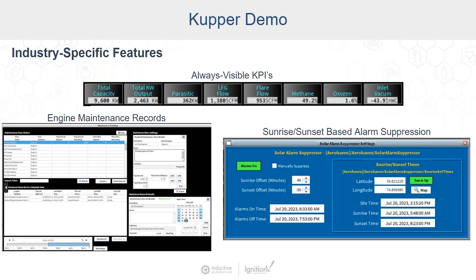For the large 70-plus solar field system, we can experience a large number of nuisance alarms as the sun goes down or comes up. We implemented a system which allows entering the latitude and longitude for the site to calculate sunrise and sunset times, combined with a dead band after sunrise and before sunset to suppress alarms and ensure that alarms received are actually important enough to act on.